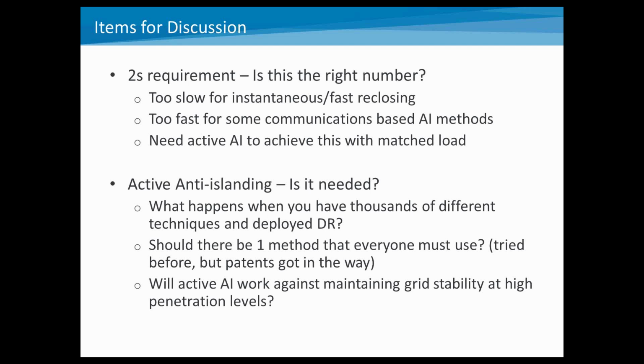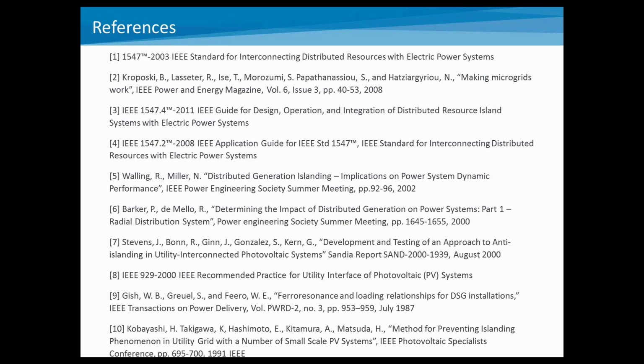Finally, as we look at higher penetrations of distributed generation, will active anti-islanding work against maintaining grid stability? I mean, the way it works right now is it's actively pushing voltage and frequency outside a normal set point. So on very weak grids, that may actually be something that's detrimental to the long-term deployment of distributed energy technologies. So those are just things for discussion. I'm sure we'll get into those here in a second.